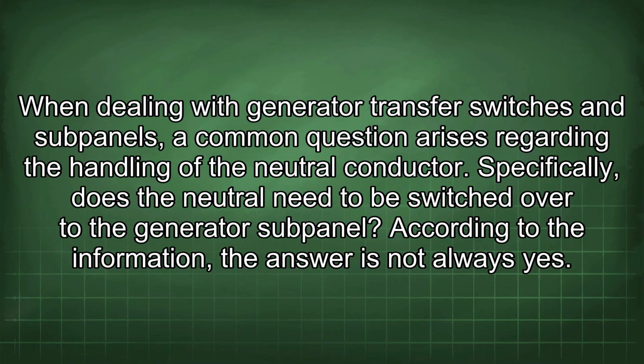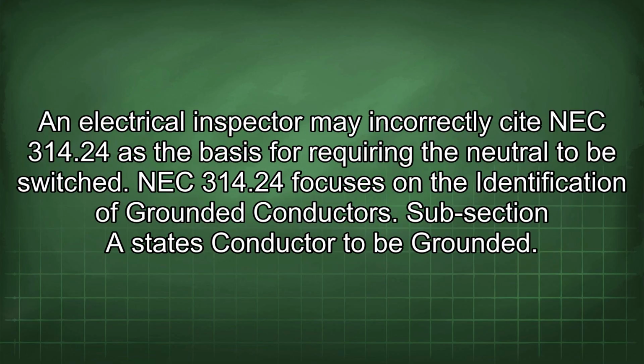When dealing with generator transfer switches and subpanels, a common question arises regarding the handling of the neutral conductor. Specifically, does the neutral need to be switched over to the generator subpanel? According to the information, the answer is not always yes. An electrical inspector may incorrectly cite NEC 314.24 as the basis for requiring the neutral to be switched.